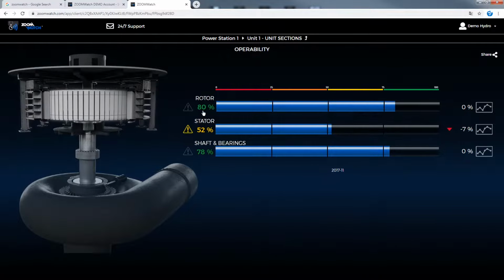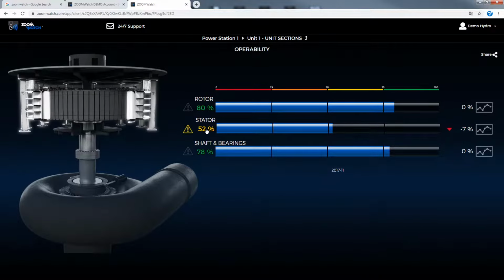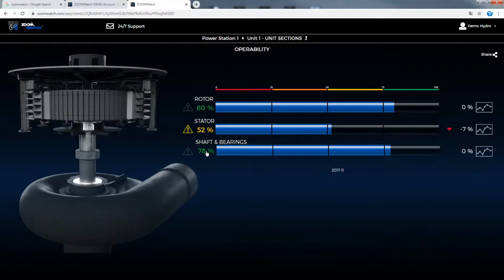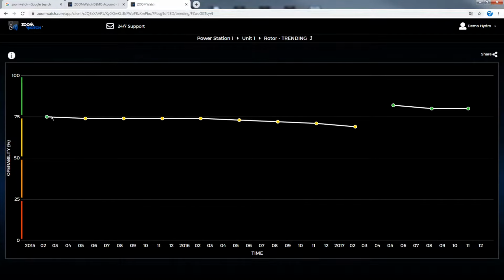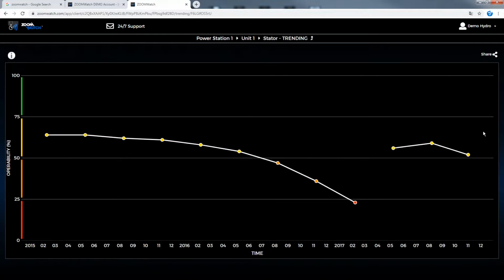You have an operability level that is calculated for the rotor, an operability level for the stator, and an operability level for the shaft and bearings. If you click on any of these, it will give you a trend over time, so you can see if there's any evolution in regards to the operability of your rotor. You can see here there's a gap. That means the unit was stopped and went to an outage, to make some corrections. And you can see the results were a little better after the outage. You can look at the overall operability of the stator, and you can see why the unit was stopped. The stator operability was going down and down and down, so they made some corrections and improved the overall shape.